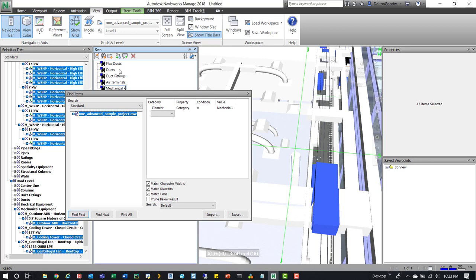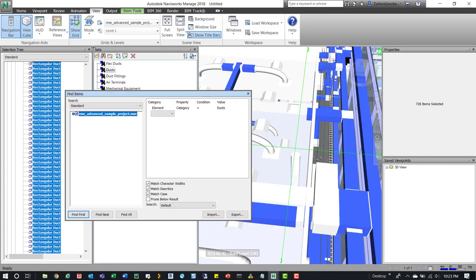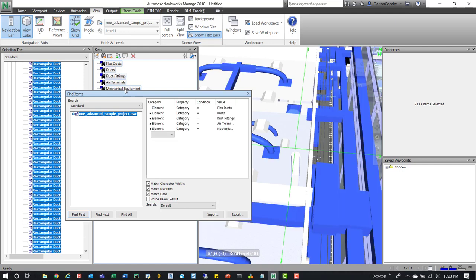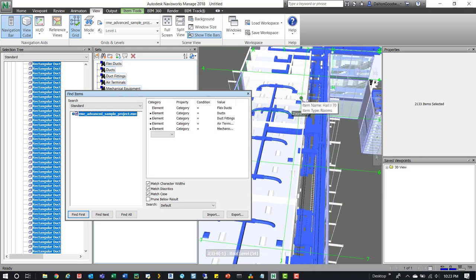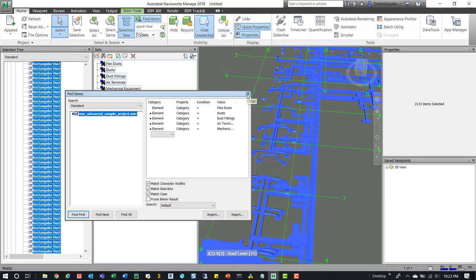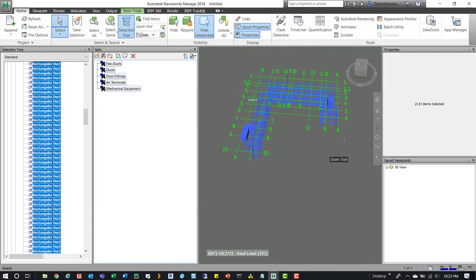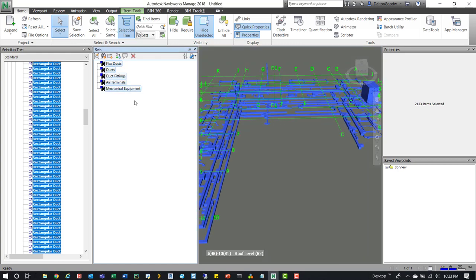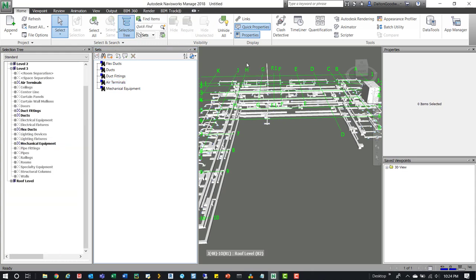If we grab all those sets and select all, we can see that entire system. Then on the Home tab we can do Hide Unselected, close Find Items, and we can see the entire HVAC system laid out. The search sets are set up, and we can save them for future use. You can either host them in an NWF file distributed to every project folder — just overwrite the NWCs and it'll have all the correct search sets — or go to the Export tab and export those search sets out.